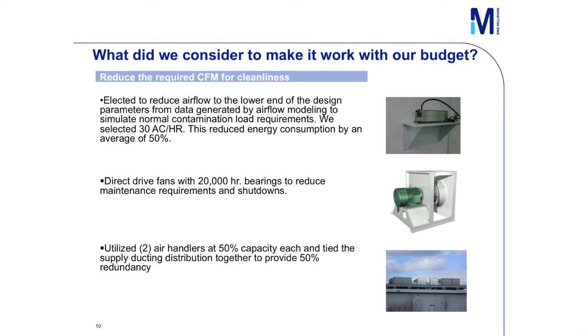That's a robustness measure we put into it. We have 2 air handlers, one a backup of the other. We run them only at 50%, so if one fails or we have to maintain it, you shut one off and we automatically open up the air to the other side of the room. Works quite well, actually. Our maintenance guys love that.